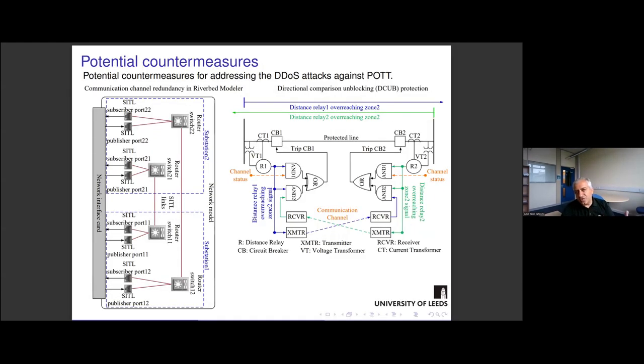So in order to address these 2 types of attacks, we started to look at the conventional approaches that we have, or potential countermeasures that we have in classic power systems. 2 simple countermeasures that already exist in classic power systems include communication channel redundancy and using more advanced protection like directional comparison unblocking protection. Directional comparison unblocking protection is another type of communication-assisted protection, but the benefit of this protection is that if the communication channel is lost, it immediately sends a command to trip the circuit breakers and disconnects the transmission line. Therefore, it may help remove the fault immediately and help the system to survive.